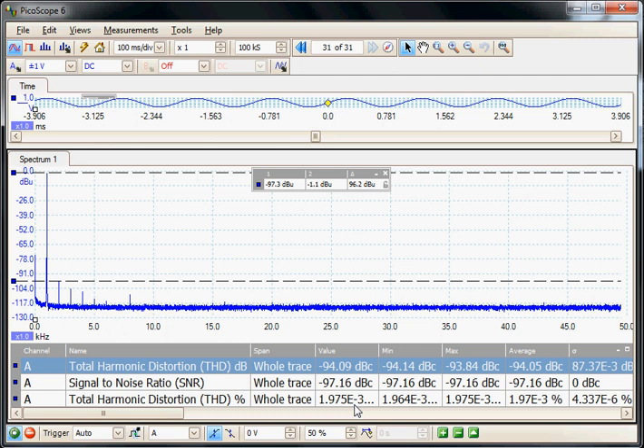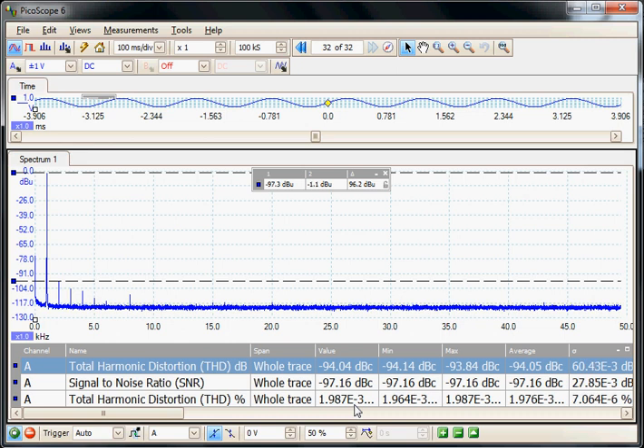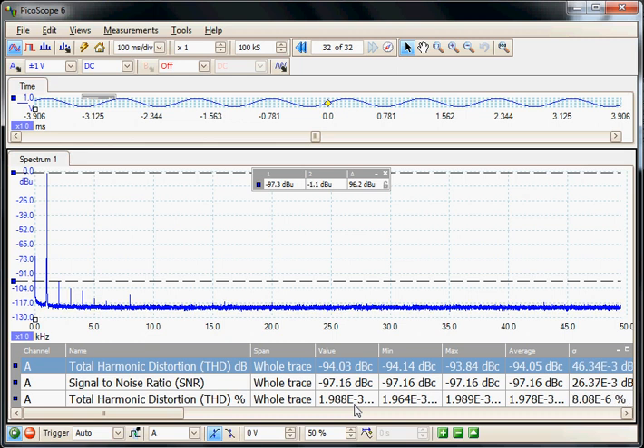So this gives us an indication of the accuracy of the measurement system. It means that any audio system that is measured, we can measure distortion from the audio system which is greater than 2 milli percent. So this will give us a very high accuracy of measurement capability.